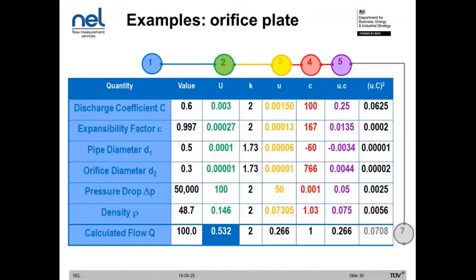We have 2 entries where the confidence level is actually different. We have coverage factors of 1.73, which is the square root of 3. These are resolution uncertainties. You can see that the manufacturing tolerances for pipe diameter and orifice diameter are resolution uncertainties. For this reason, we have different K values for those 2 inputs to the uncertainty table.